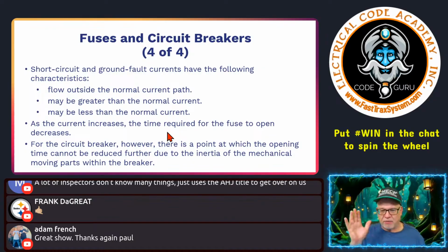And again, this takes care of itself, but it's just something that you know, that short circuits and ground faults typically result in current potentially traveling on paths that they weren't intended, which is energizing metal parts in many cases. That's why we bond. That's why we do what we do. Okay, and that's why overcurrent protective devices have to be sized so importantly, and you don't overfuse stuff. That's why you don't stick the penny behind the S-type fuses in an old panel board.